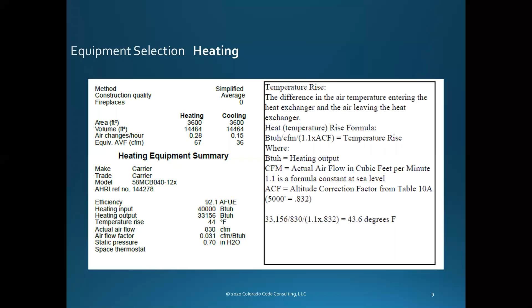And just a quick example of what temperature rise is. So basically we've got this return air that's coming down. Look at that, nice big box on the bottom of that furnace. So you've got a temperature probe up here. What's the temperature of the return air? You've got a temperature probe here somewhere, that's a big coil, temperature probe there. Then what's the difference? So what's my temperature rise? How much is it warming from here to here? And if the temperature rises within that range, the furnace is working. If it's not, it can be too hot and it can be too cold.